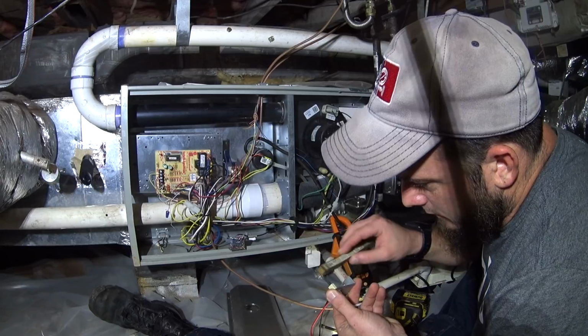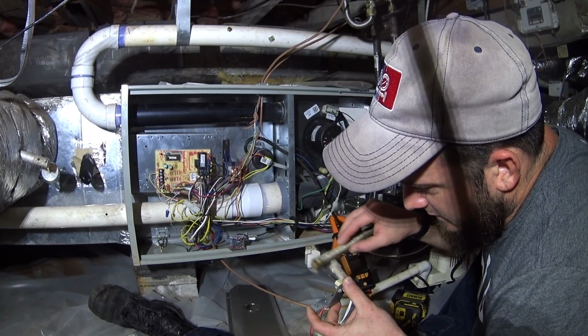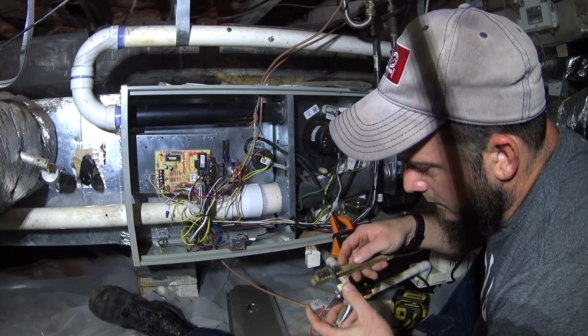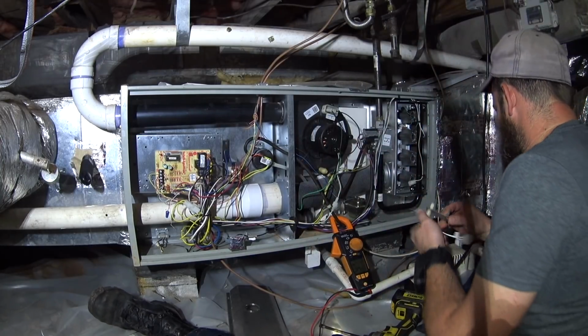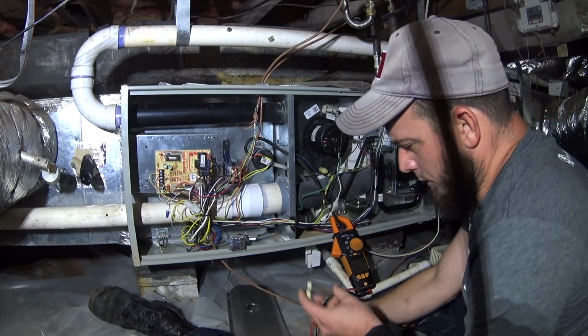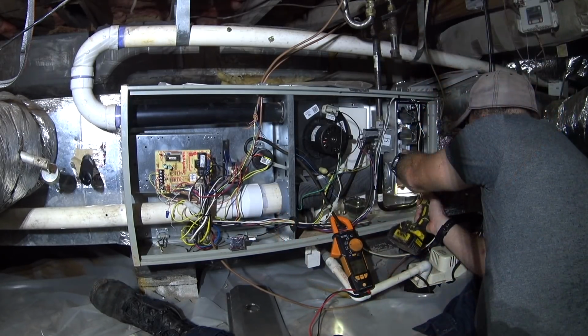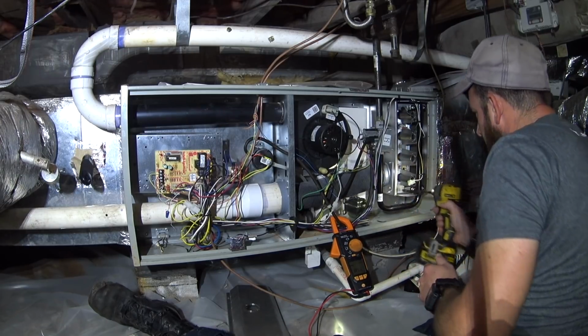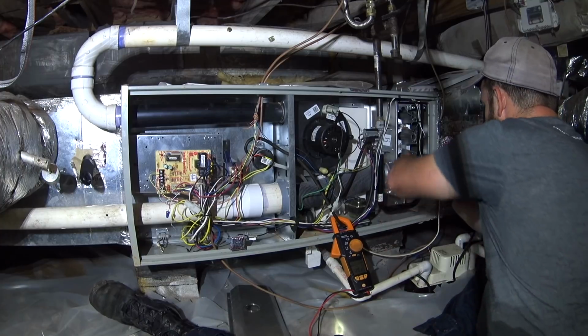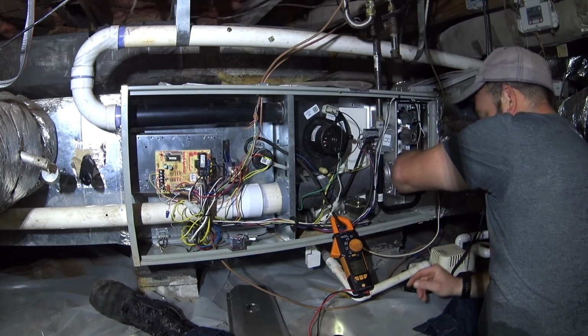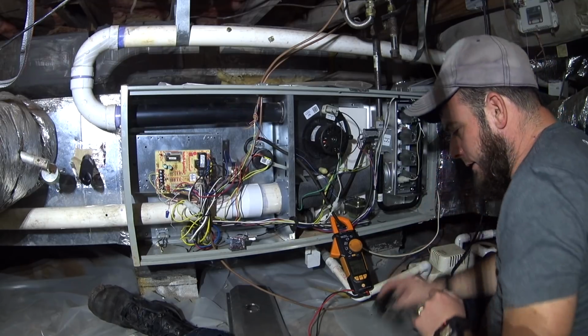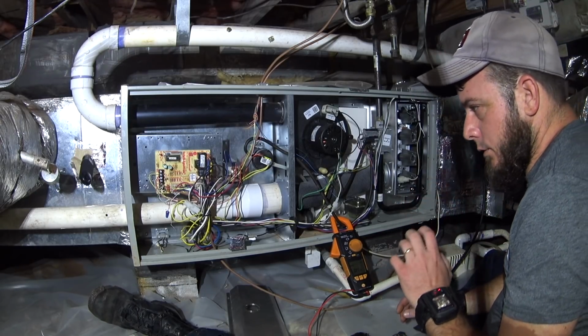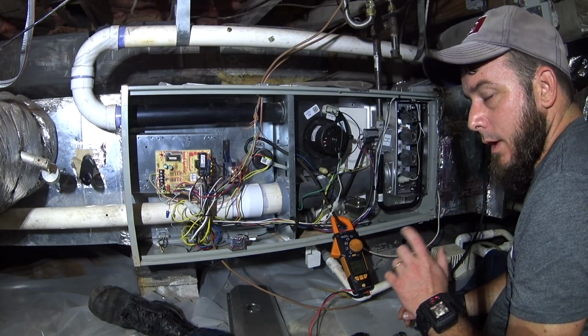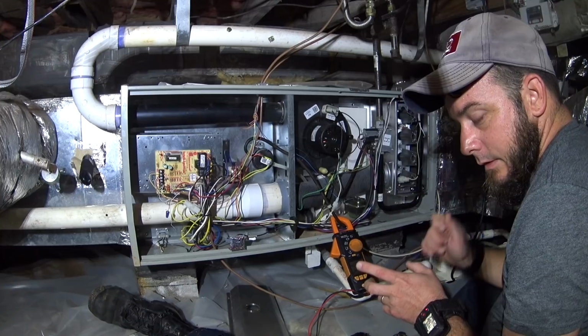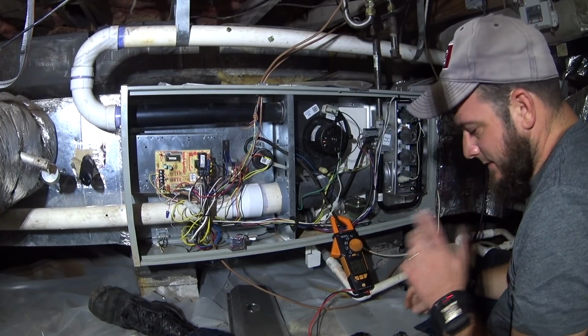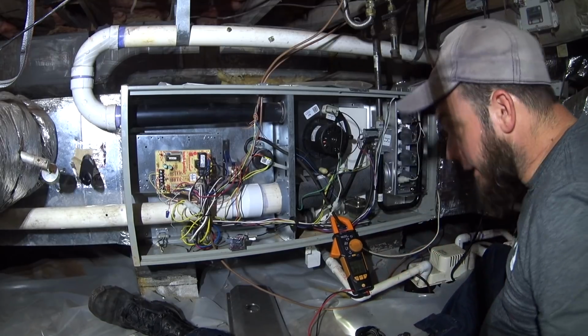Maybe I shouldn't clean these at all, but it seems like any resistance that may be added by collection on the burner is a good thing to get rid of, or the igniter. You want to be careful when you're mounting your igniter with an impact driver, especially, not to impact the screws to the point where you could crack the igniter. I have put in brand new igniters and the screw didn't thread smoothly and broken brand new igniters right off the bat.